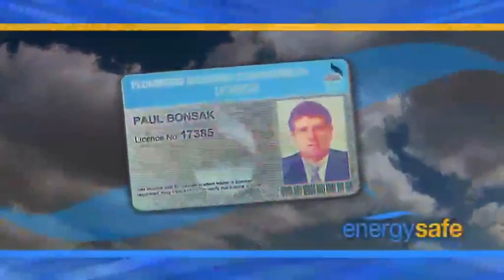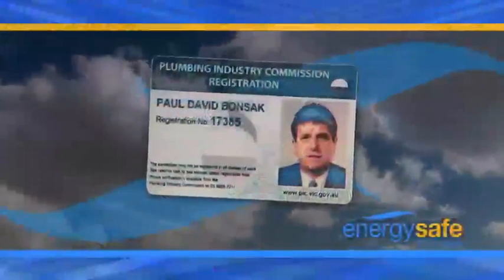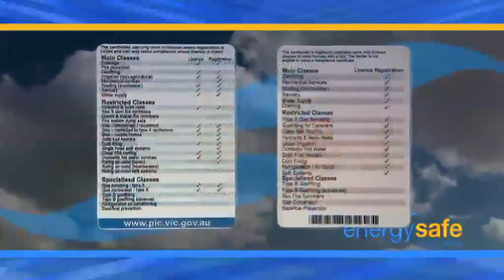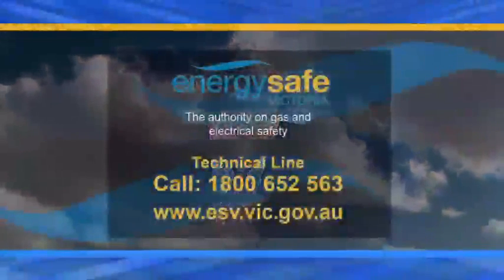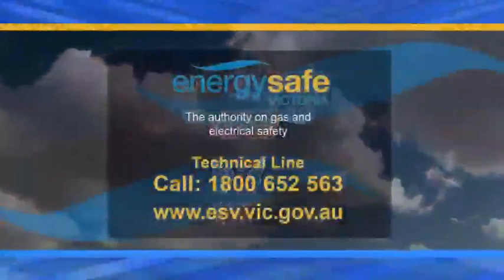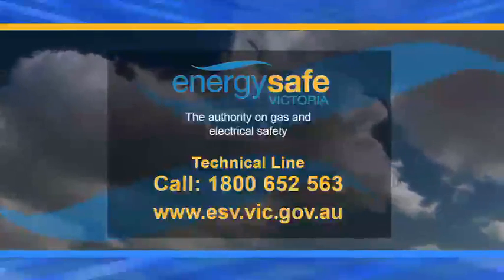Not everyone can service a Type A gas appliance. You must be licensed or registered as a gas fitter in gas servicing Type A with the Plumbing Industry Commission. You will need a CO analyzer or detector to complete the safety inspection. This DVD will show the gas fitter the procedure they must follow to test for carbon monoxide spillage from a gas heater. If you have any further queries, please call our technical information line, which is on your screen now.